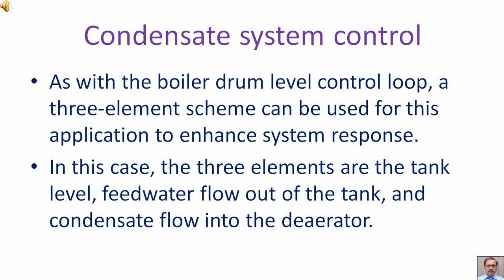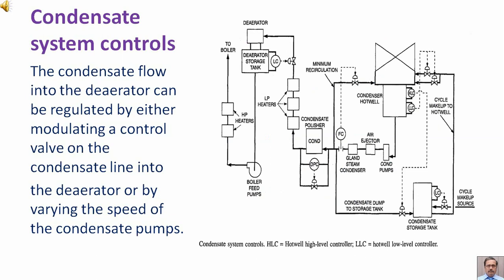In this case, the three elements are: the tank level, feed water flow out of the tank, and condensate flow into the deaerator. The condensate flow into the deaerator can be regulated by either modulating a control valve on the condensate line into the deaerator, or by varying the speed of the condensate pumps.